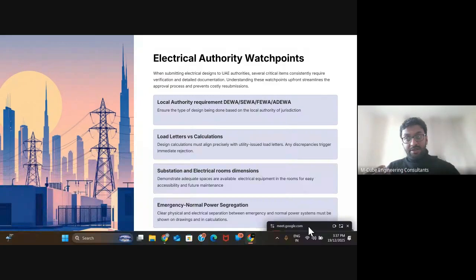One reason for rejection is when units are not consistent. When submitting for Sharjah, loads are in kVA, so ensure the same is shown on your drawing for easy review. When submitting for Dubai, it is in kilowatts. You need to ensure you're submitting the proper loads on the single line diagram as well as on the calculation and authority forms.